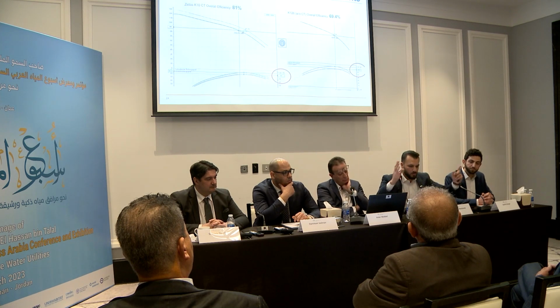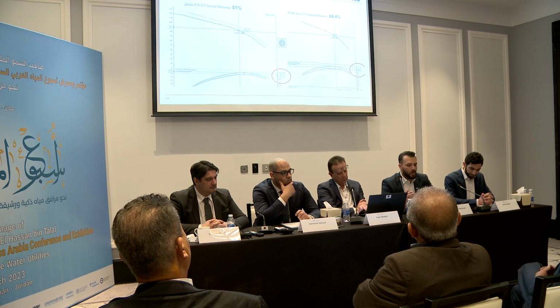Taking these two examples with the curves of the pump, you can see the overall efficiency is 81% for the new improved pumps compared to 69% before. With the previous electricity tariff in Germany of 0.17 euro per kilowatt hour, you get back your investment in 3 years. And this is with low energy cost - it will be even faster as electricity becomes more expensive. So this is an example I wanted to share regarding the efficiency of the pump and the system.